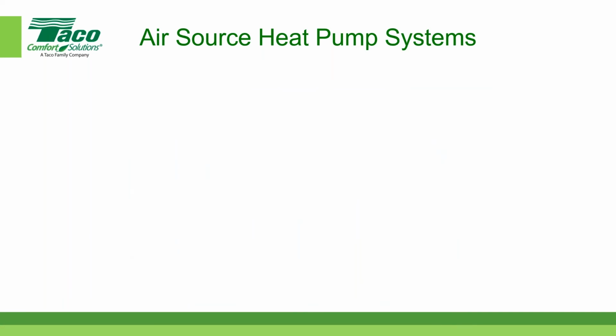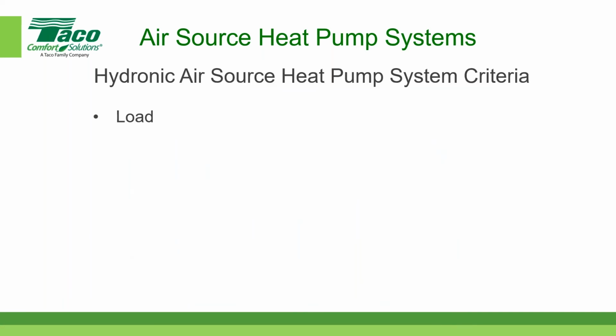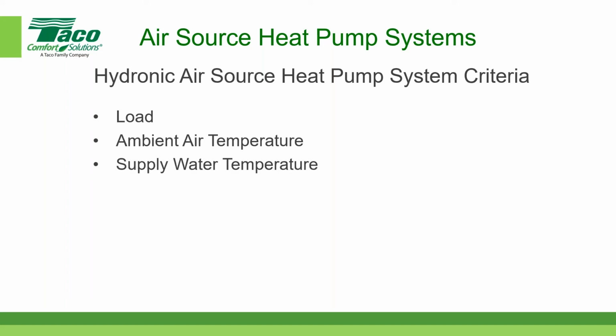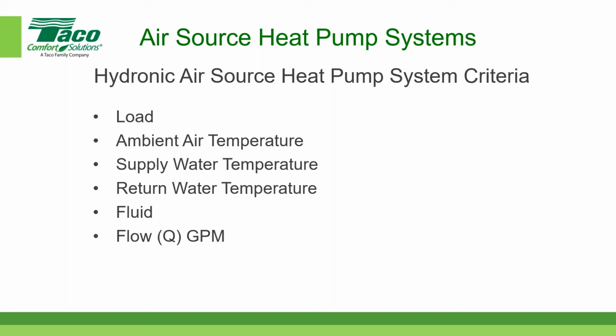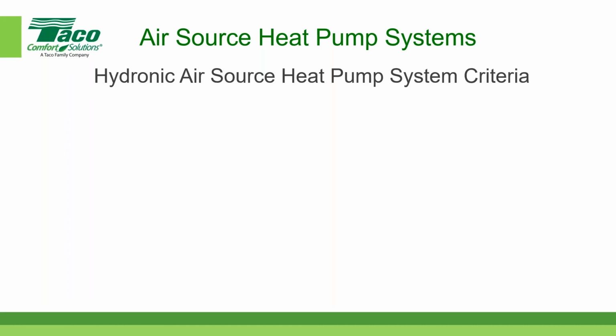Okay, so let's look at a diagram. Oh, let's look at criteria first. So first we need to know what the load is when we're designing a system. Then we need to know what the ambient air temperature is. We need to know what the supply water temperature is, the return water temperature, and the fluid. And in our case, we'll just say it's water or water glycol, rather than some kind of exotic fluid. We also have to know the flow of the fluid in gallons per minute.